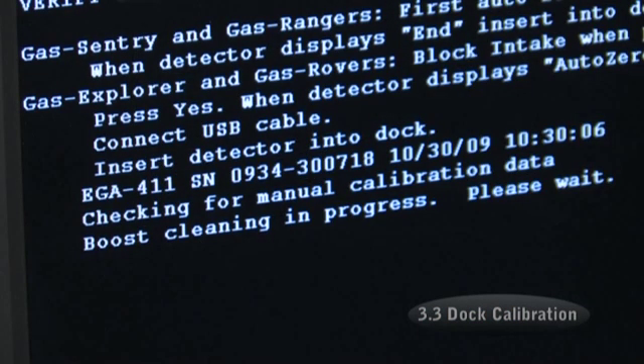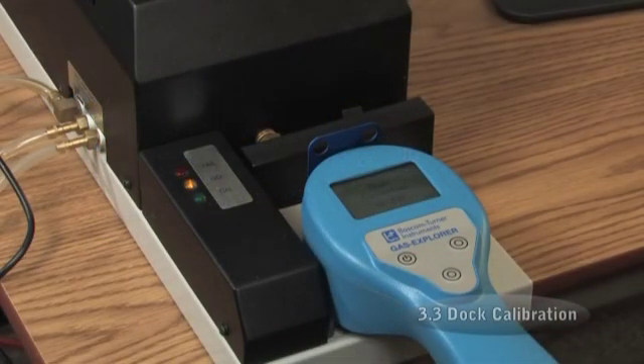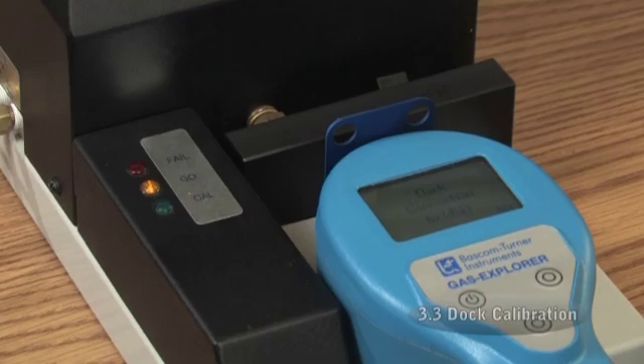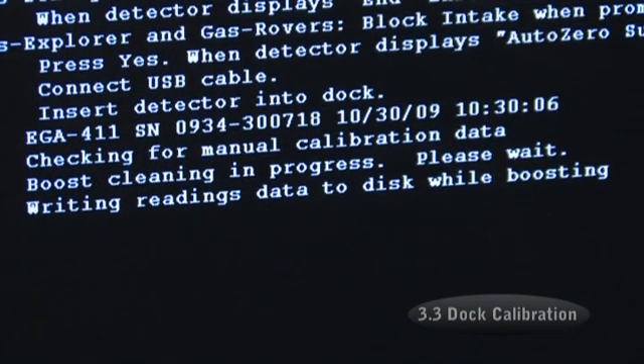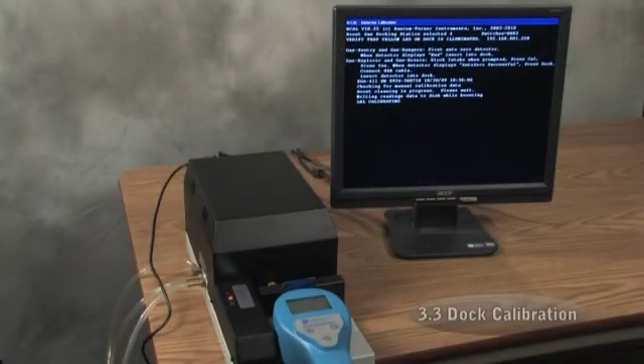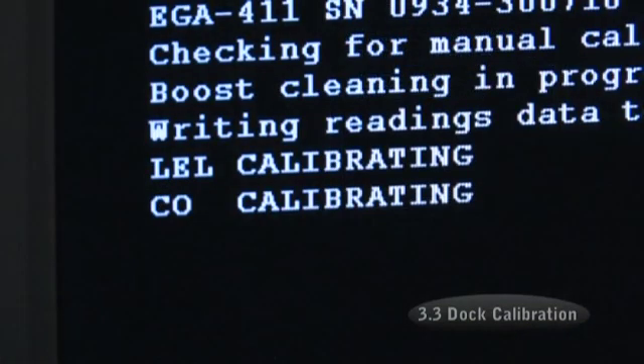Shortly after, you will see confirmation on the monitor that the calibration process has begun, along with flashing of the Dock and Explorer LEDs. The model number, serial number, date, and time will all be displayed. From this point, the calibration process will proceed automatically. Indications of gases being dispensed will also appear on the monitor.